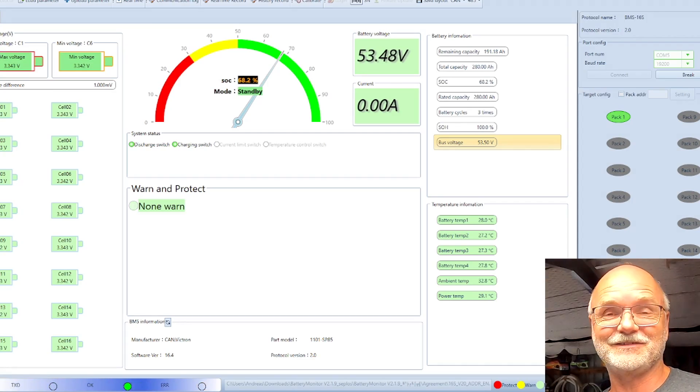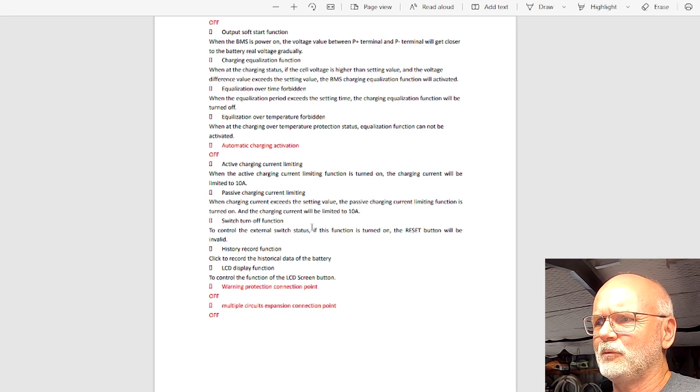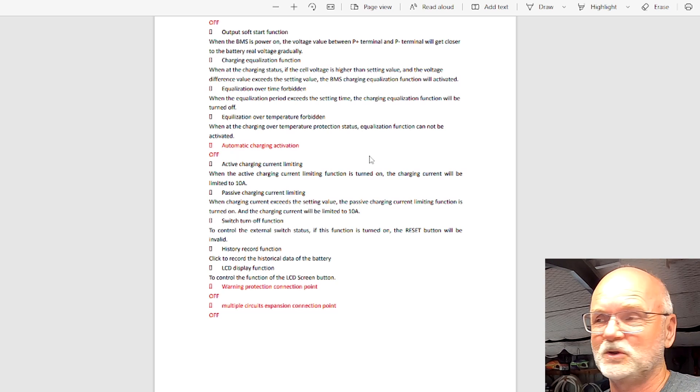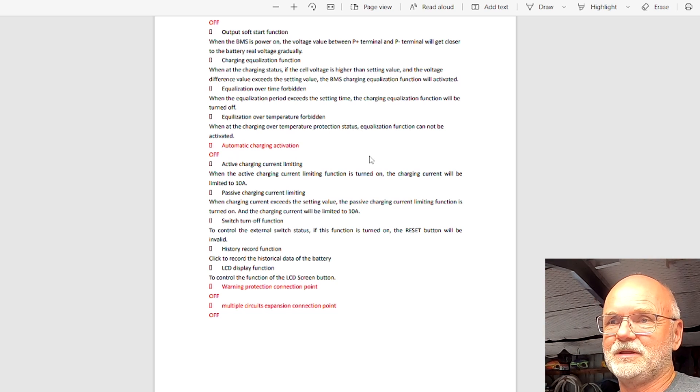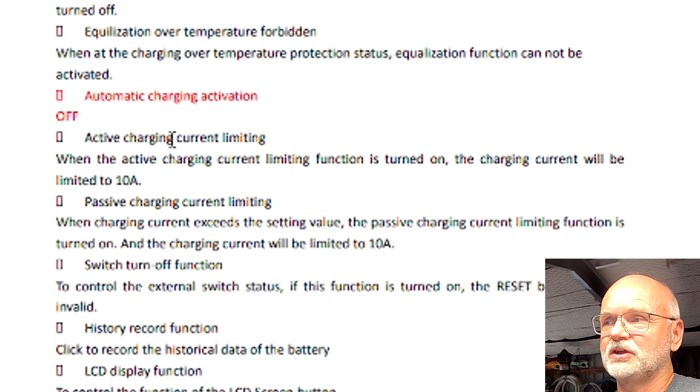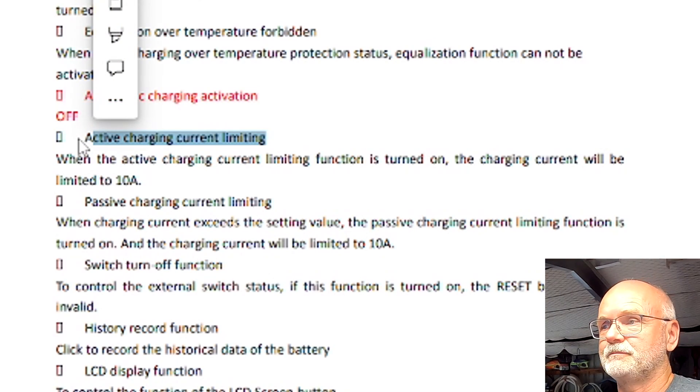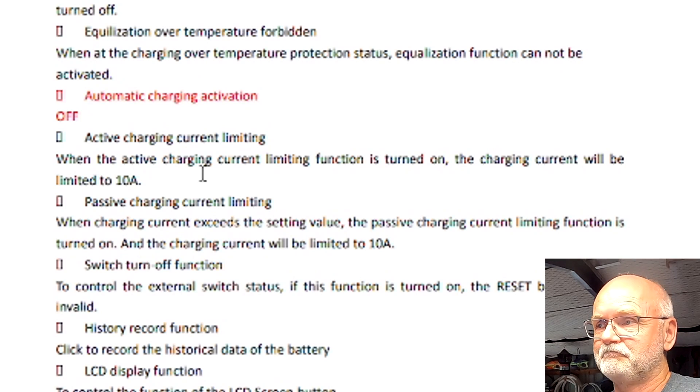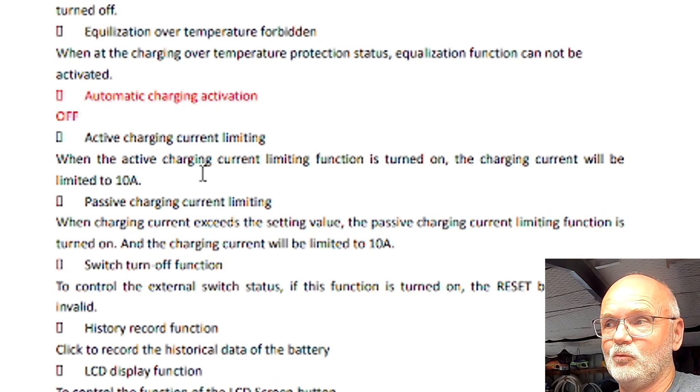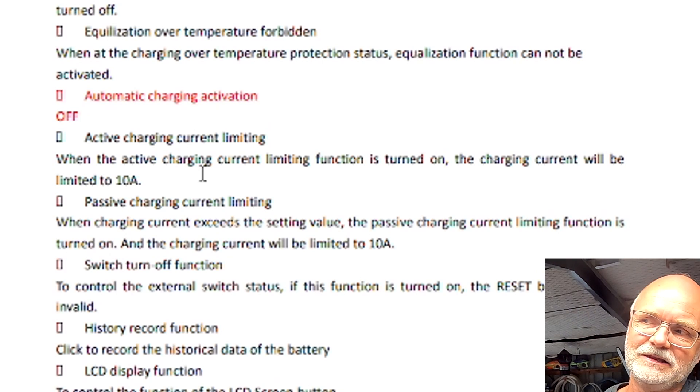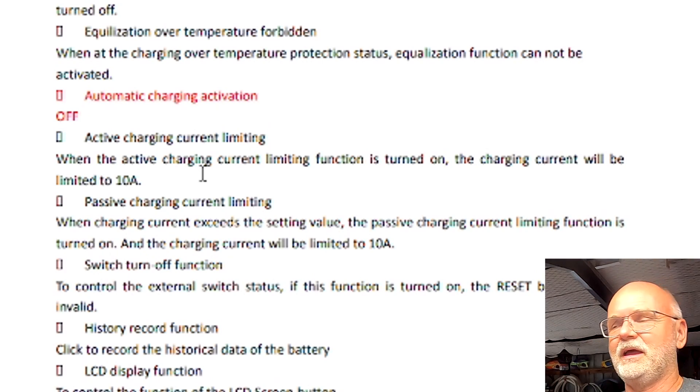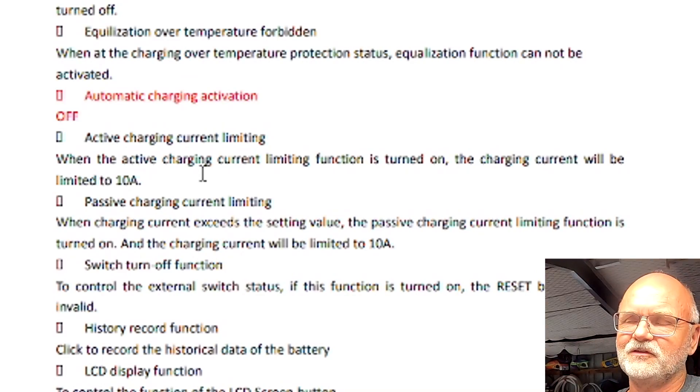Welcome back, it is now the next day. I actually had to contact SEPLOS because I had a look in the list they provided us with a couple of weeks ago with all the function switches of the BMS explained. I could not find the 'take the initiative limiting charging' function switch. I got back to them and they replied this morning and said, depending on the BMS and the software version it may have a different name. In the list it is called 'active charging current limiting.' It says here when this charging switch is activated the charging current will be limited to 10 amps only. I asked back and said why, what is this switch for? He said it is more like for testing purposes. If you have a big solar array and you want to test something and you want to limit your incoming current from 150 amps to only 10 amps, this is what the switch is for.